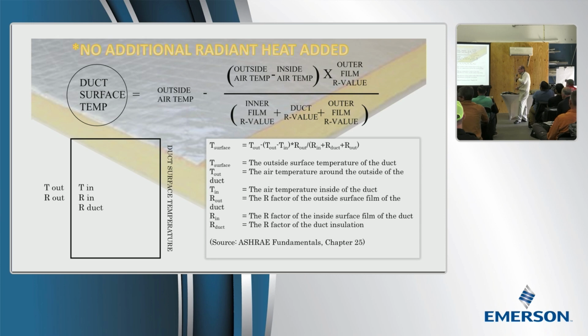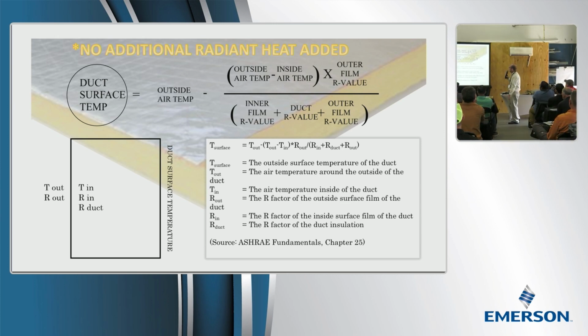This is a basic formula for determining how cold the duct is going to be. Because we already said, if we're in climate zone 1 and the duct gets cooler than 73, it's going to get wet in the summertime. So we could use this formula, but I'll point out this is a very simple formula that doesn't include any radiant heat—in other words, this is just conduction. So this would be the temperature of the duct, maybe if it was in an attic with some heat coming down, it would be on the bottom. Generally, it'll be, if anything, warmer than this.